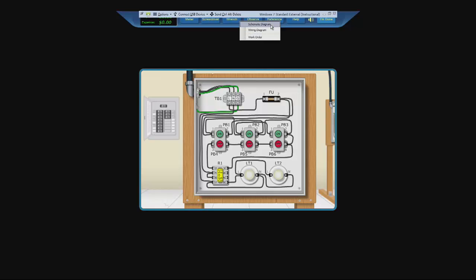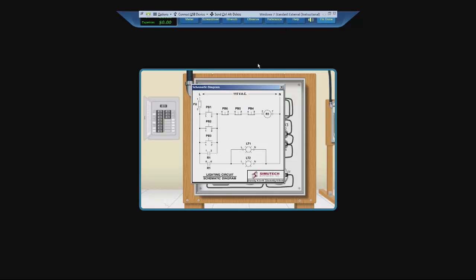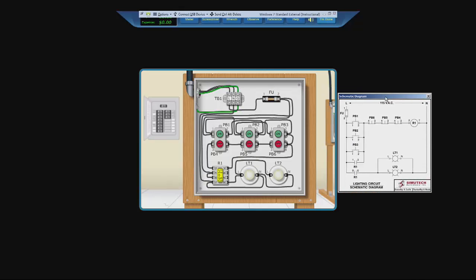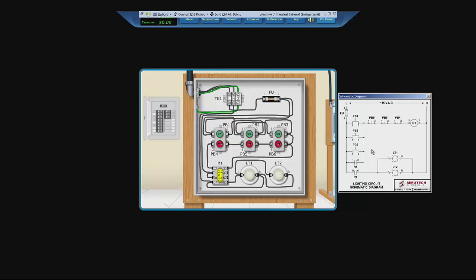And if we go to reference, schematic diagram. Pull this over. Turning on any of the push buttons would activate relay one, closing this and sealing it in, and turning on the lights. As this has not happened, something else is wrong with the circuit.